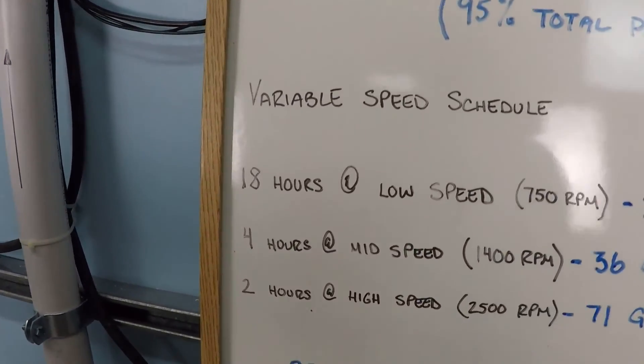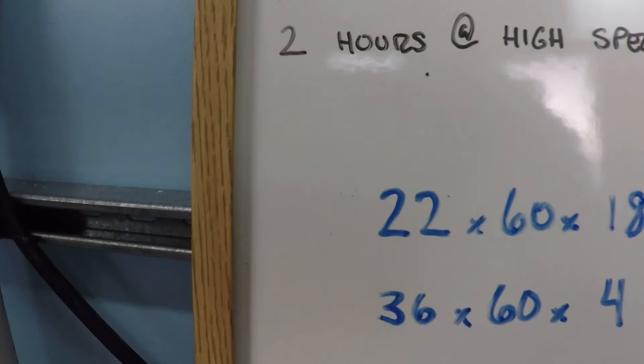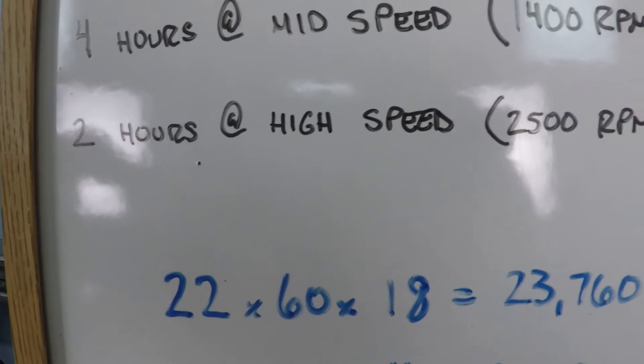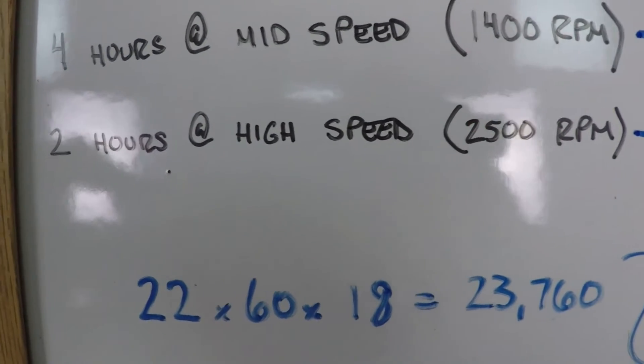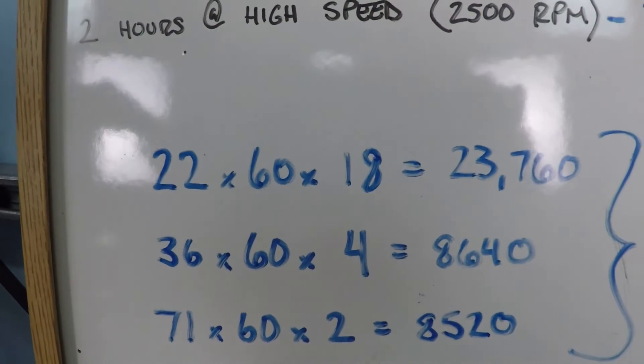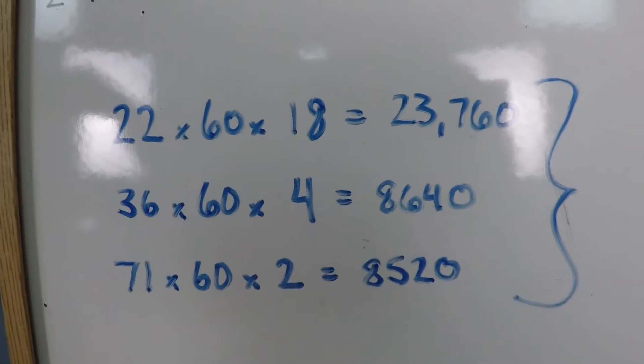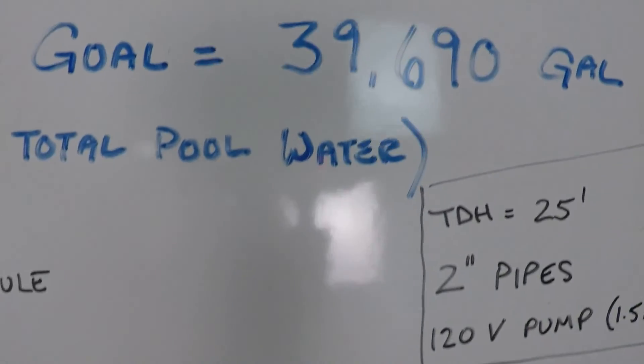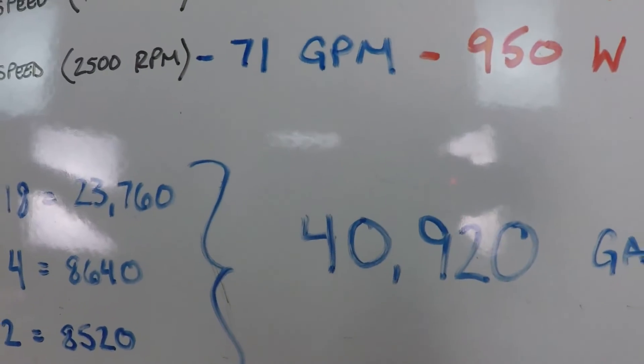So let's talk about these numbers just a little bit. So first of all, the flow: 22 gallons per minute times 60 minutes in an hour times 18 hours a day for the low speed operation, 23,760 gallons just from the low speed operation. 36 gallons per minute times 60 minutes times 4 hours, 8,640. And 71 gallons a minute times 60 minutes times 2 hours is just over 8,500. So the grand total here is 40,920 gallons. Our goal was 39,000. So we overshot by just a small amount and that's just fine. 40,920 gallons.